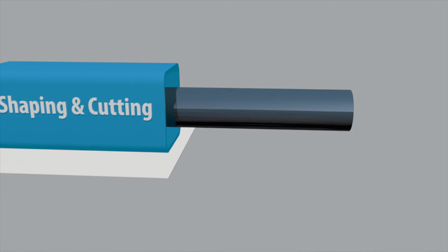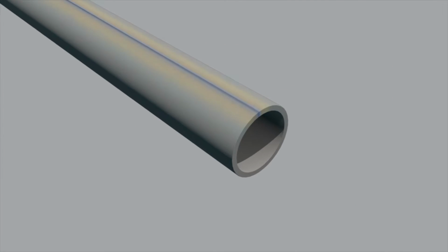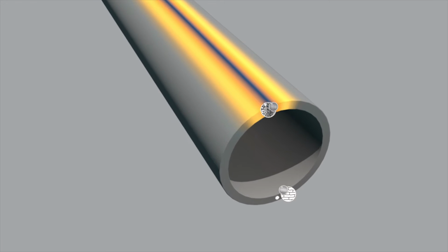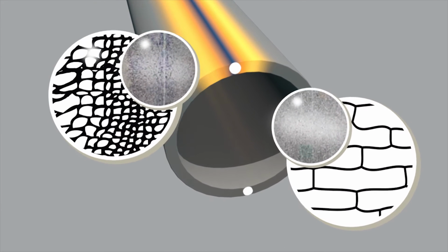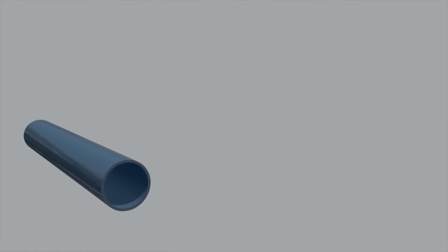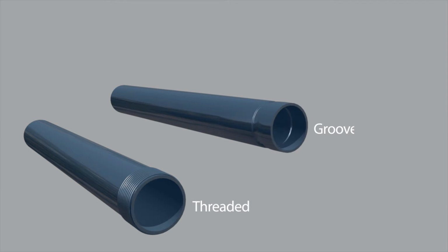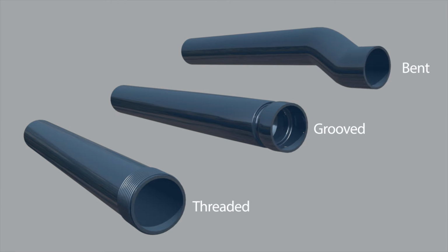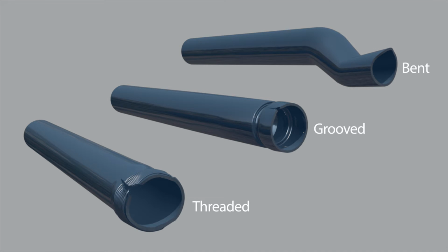Welded cold form tubes have a heat affected zone, an area of weakness around the weld region where the microstructure of the steel is distorted and prone to internal stresses and inconsistent mechanical properties. This can lead to fabrication, installation and service life issues, and can increase the risk and costs of projects.